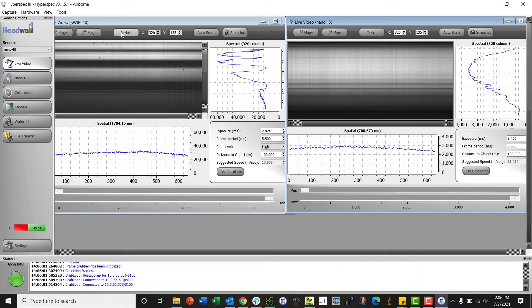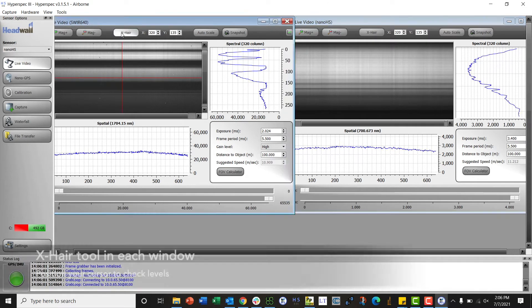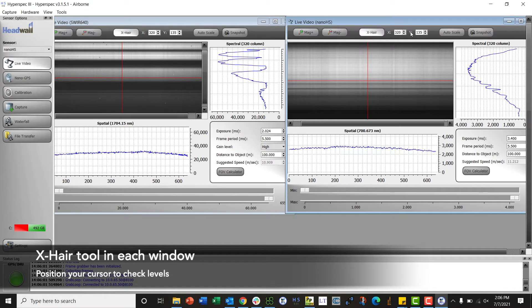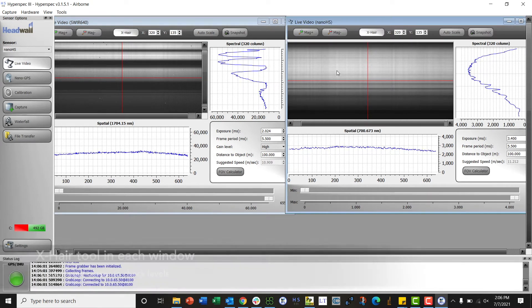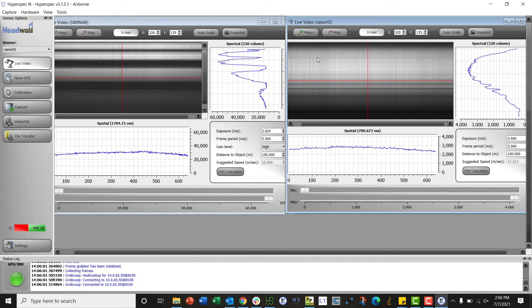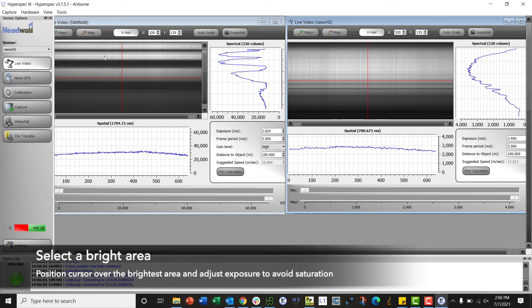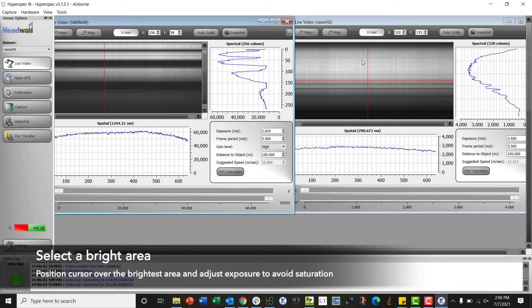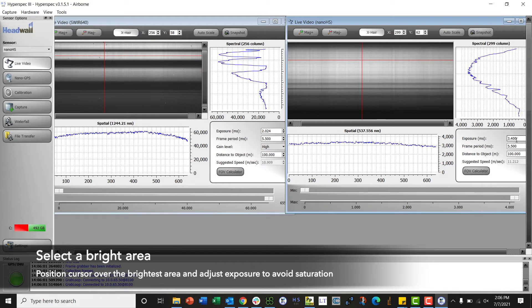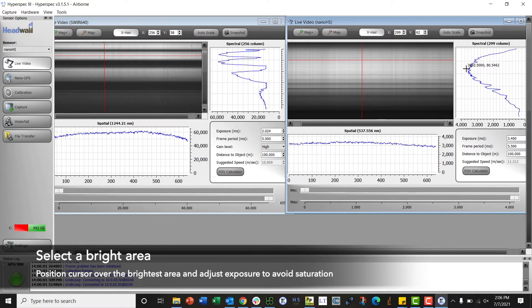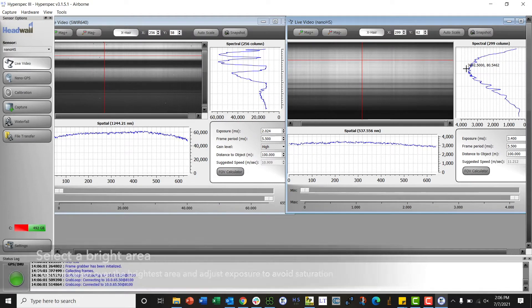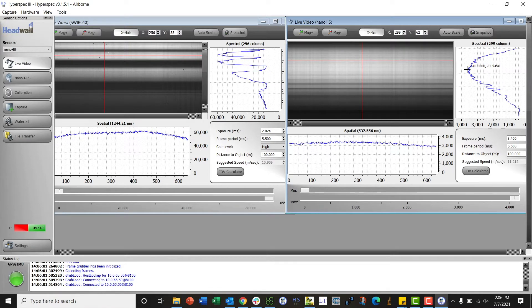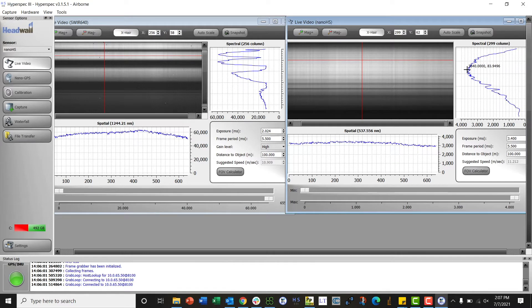Now we are looking down at our white reference which is fully illuminated by the sun. First thing I want to do is click this crosshair button on both sensors. That shows me which pixel this plot is displaying for, and I want to make sure that I'm not in a dark region. Now I will adjust my exposure. For the Nano I want to be looking for about 3500 to 3800 counts. If I hover over the top of this peak it's telling me we are at about 3600 counts, so I'm okay with a value of 3.4 for my exposure.